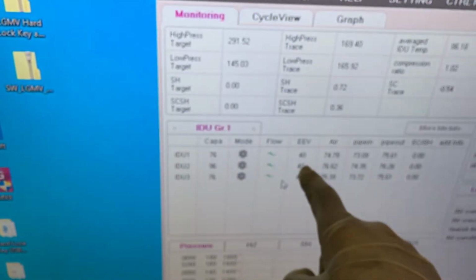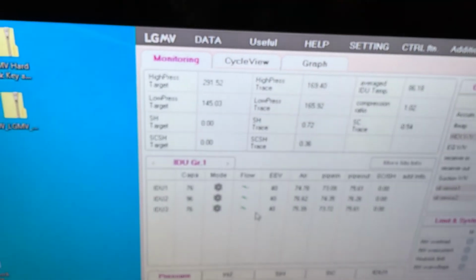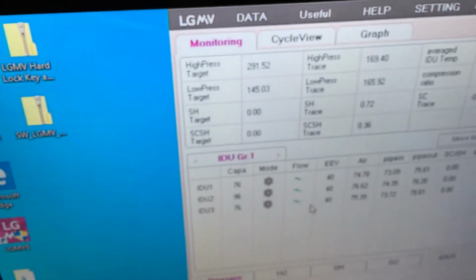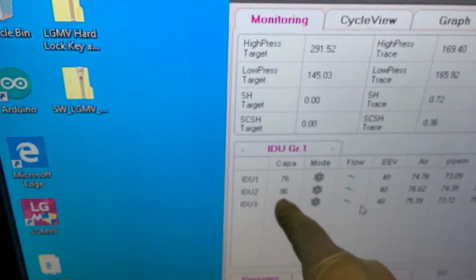And so the customer will have both his units up on the wall. So it's constantly running 24/7. And as the customer turns equipment on and off in the unit, he can literally see his compressors wind up and down. As we can see here, the expansion valves are doing nothing because everything is in the off state, so it's only open minimally to a 40 count. And you can see we have 2 6-tons and a 9-ton on this one heat recovery unit up on the roof, and this is exactly mirrored to this system.